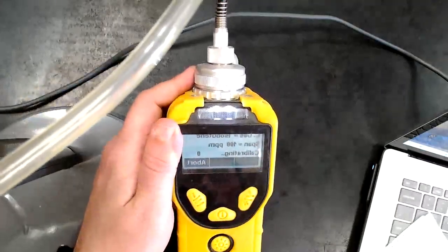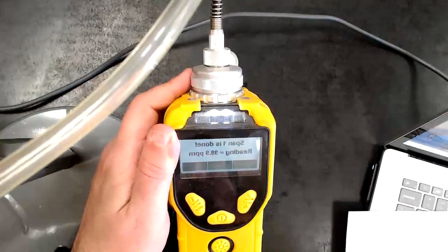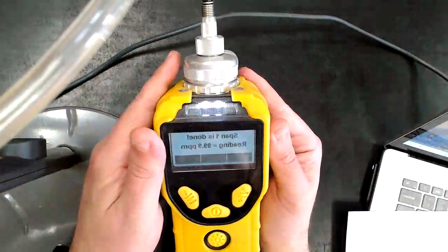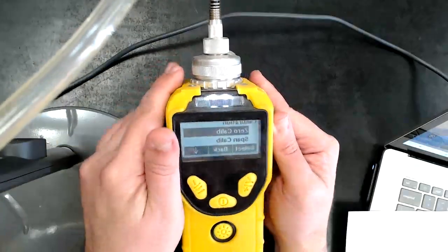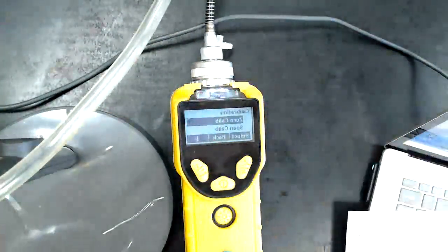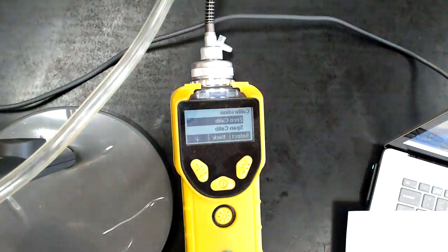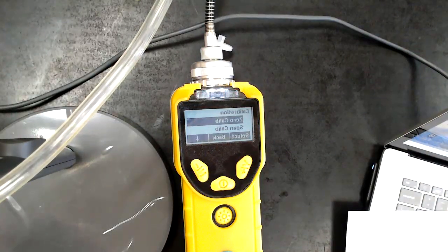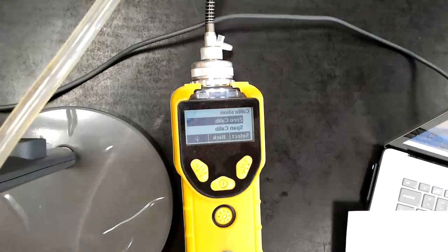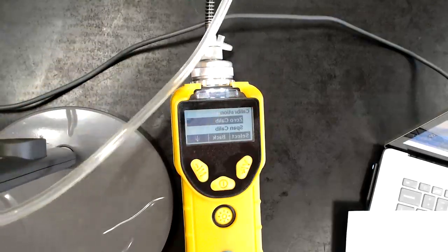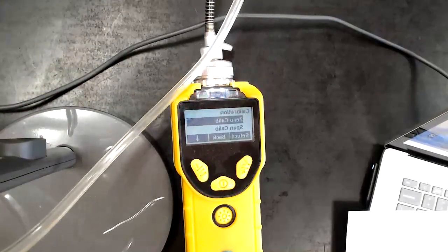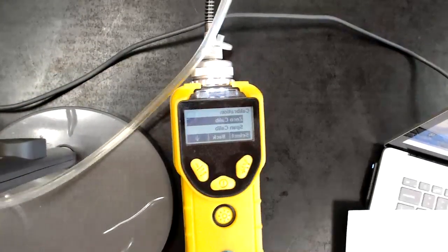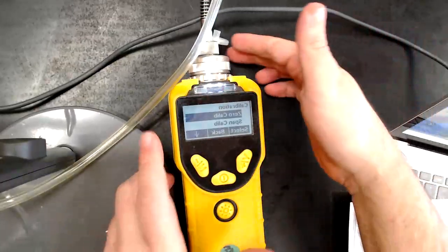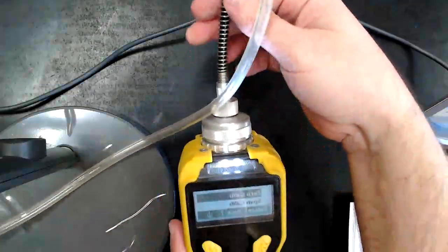We've got one more second. It looks like we're there. The span calibration is done. I want to shut off this span gas so we're not wasting it. We have the zero calibration and the span already done. I want to take this off and go back.